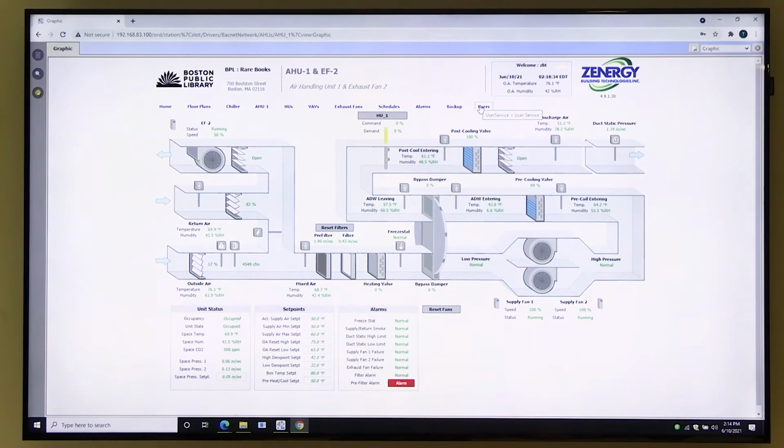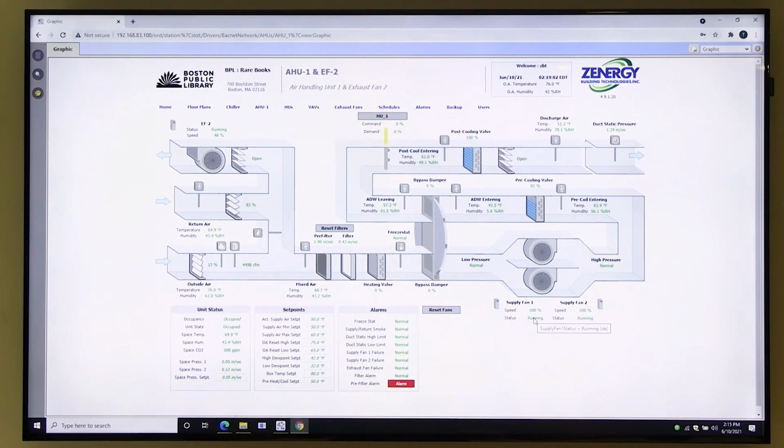Okay. To the extent we can automate that, that might be good, so we know when something's going on. Is there any way you can throw an hour timer on that? Kind of like we would do with pumps, like lead lag, just to see run time, so instead of using a date, we can say we did maintenance at 500 hours or whatever. Like an actual runtime, I gotcha. Just off a CT or something.